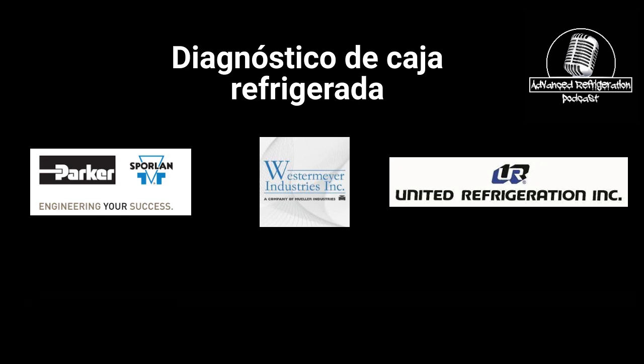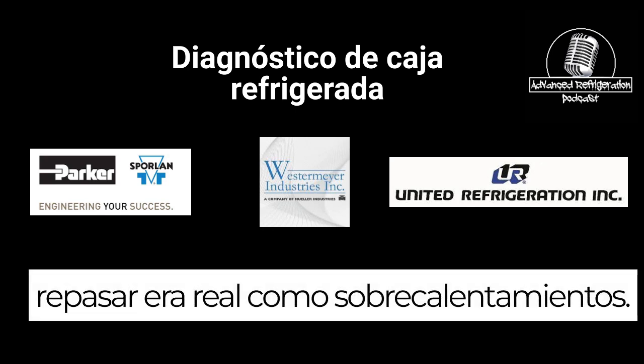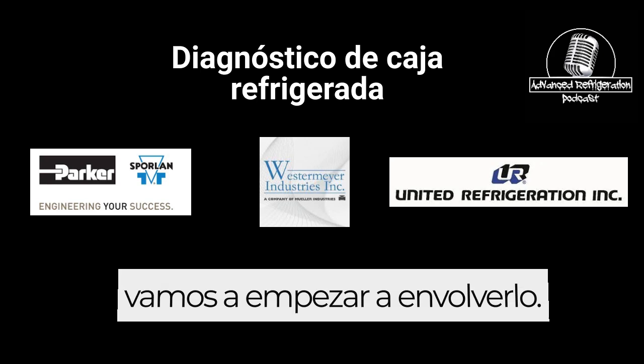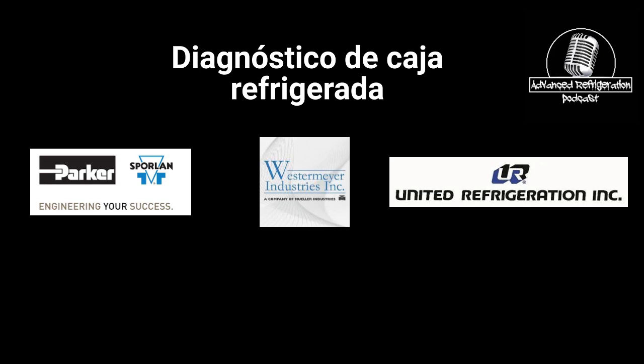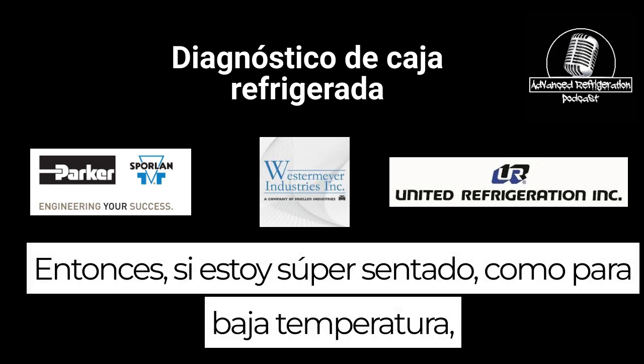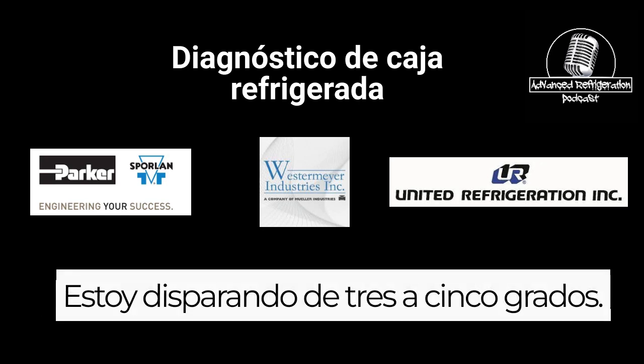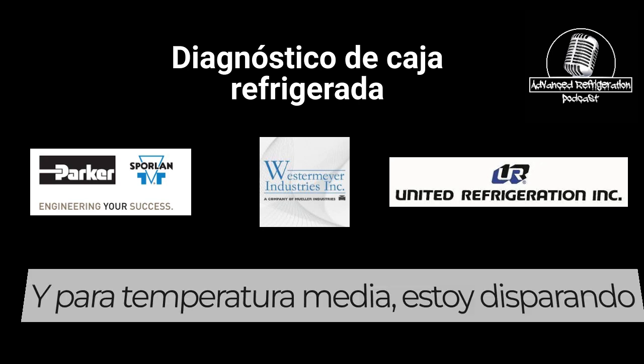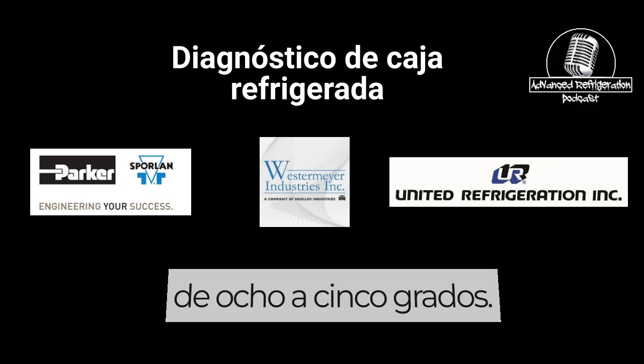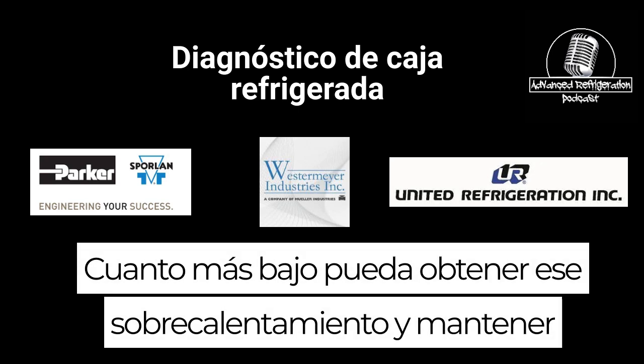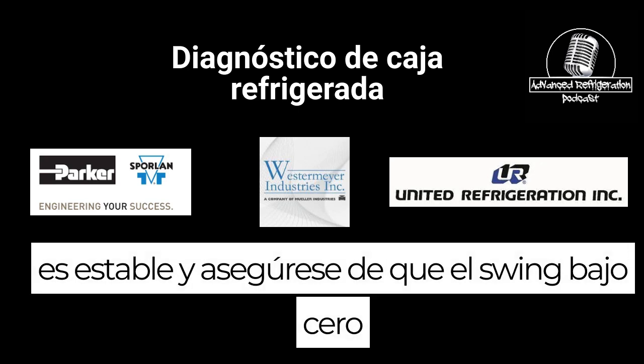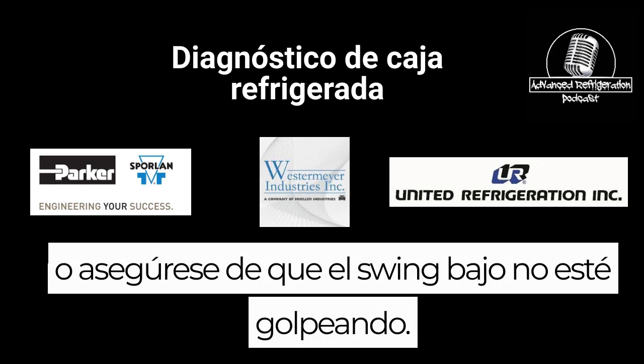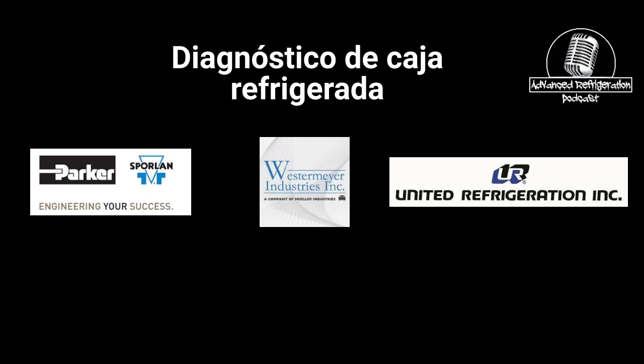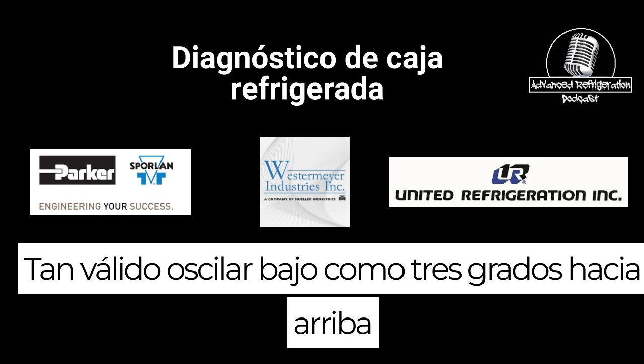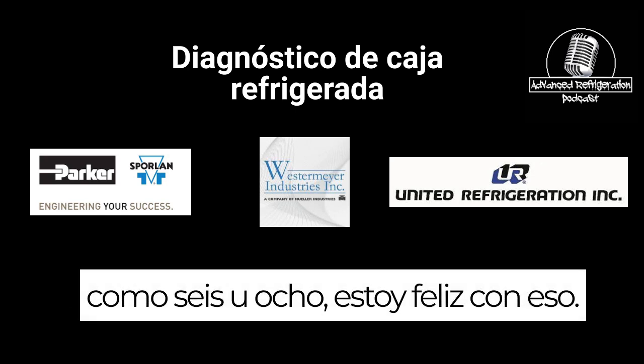The last thing I wanted to go over was actual superheats. So we'll make this real quick, and then we'll start to wrap it up. If I'm setting superheats for low temp, I'm shooting for like 3 to 5 degrees, and for medium temp, I'm shooting for like 5 to 8 degrees. The lower you can get that superheat and keep it stable, the better. I try to aim for my low swing, the valve swinging low, to like 3 degrees, up to like 6 or 8. I'm happy with that.